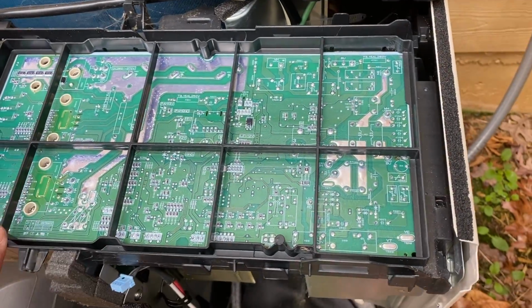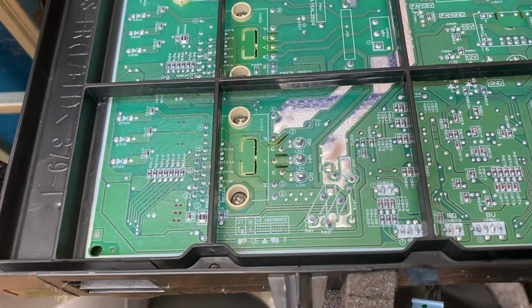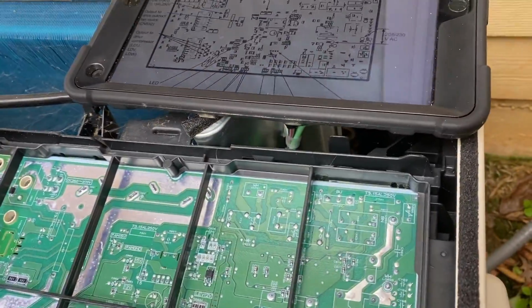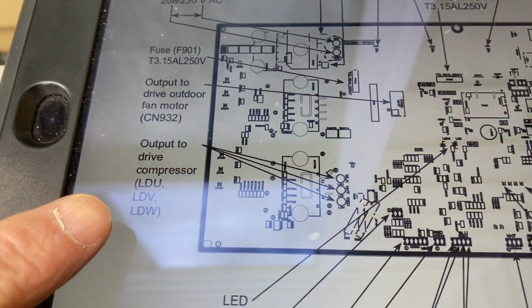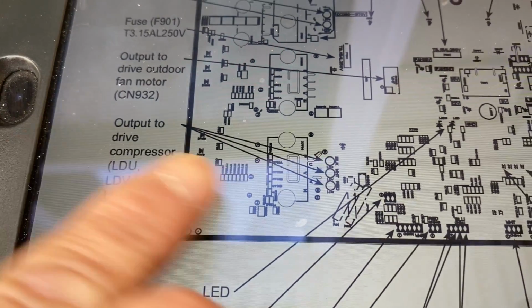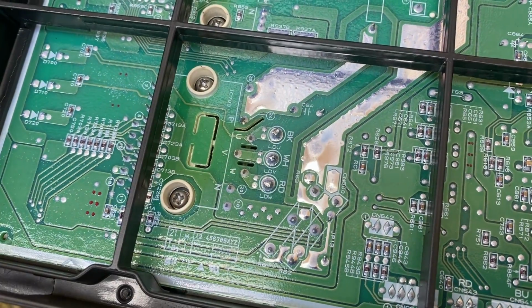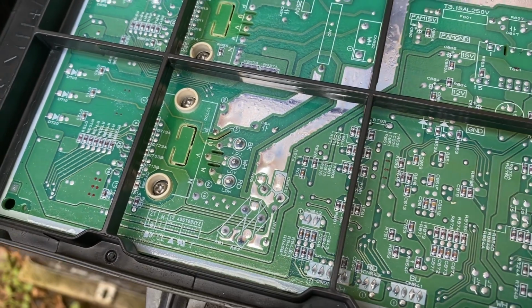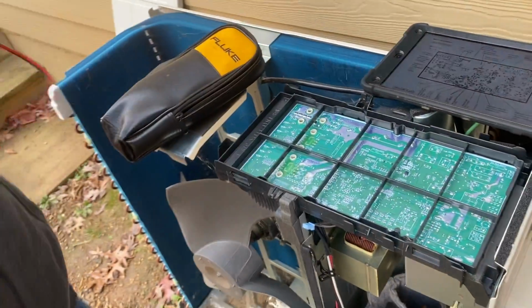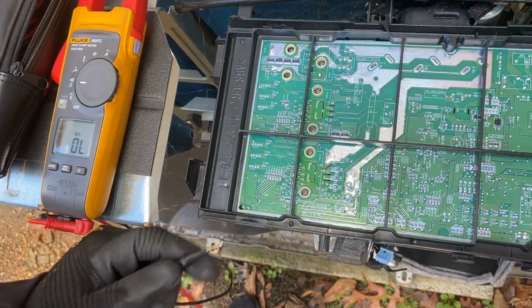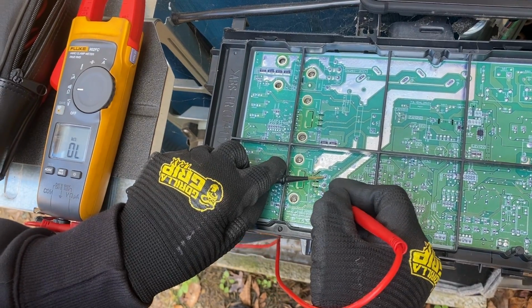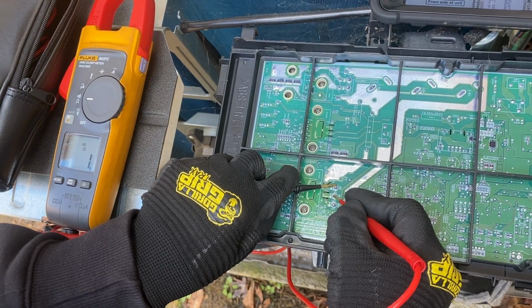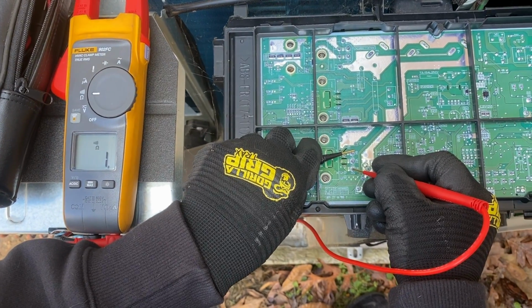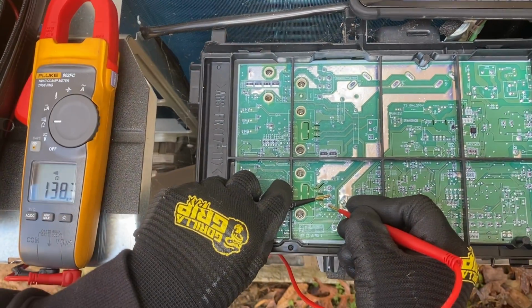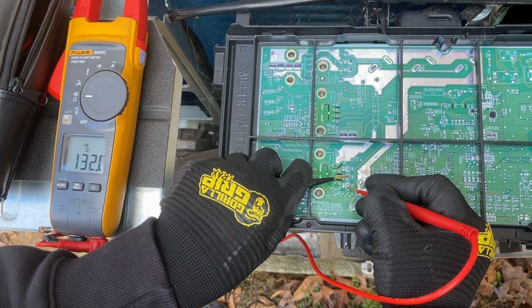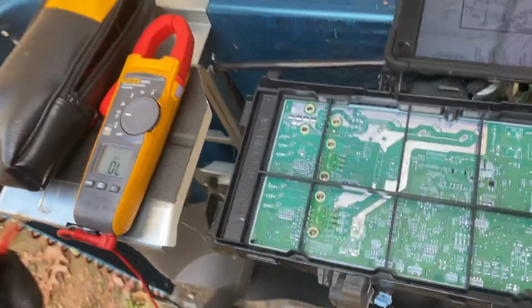And if you wanted to check your compressor, if you want to ohm your compressor out, let's go ahead and do it right quick. How do I know where my compressor is? Well, right here, output drive to compressor, U, V, W is right there. So if I wanted to ohm my compressor out, all I would have to do is get my trusty meter right here, put it on ohms. So if I wanted to test the compressor, you go from black to white. We got 1.3 ohms, or 1.1. Then we go black to red. We got 1.1 ohms. And then white to red. We got 1.5 ohms. So that's how you test the compressor.